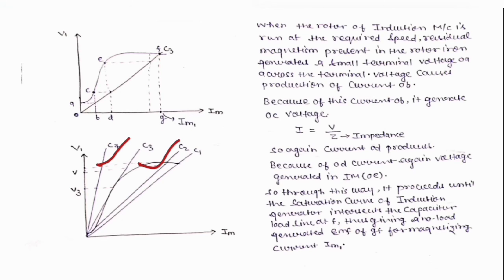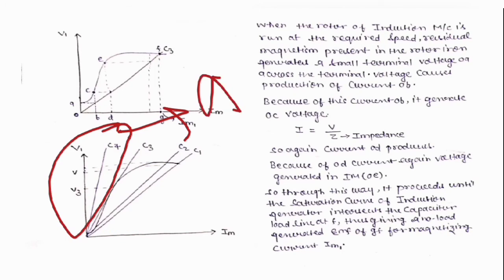If somebody says okay, I have given reactive power, so the magnetization is created, so we will get the voltage developed at the induction generator side. But that does not happen if the magnetization curve is not touched by the reactive power supply line. In that case we do not get any voltage output at the output of the induction generator. This is the important thing actually, you will have to consider it. This is the important one, okay, from this graph.